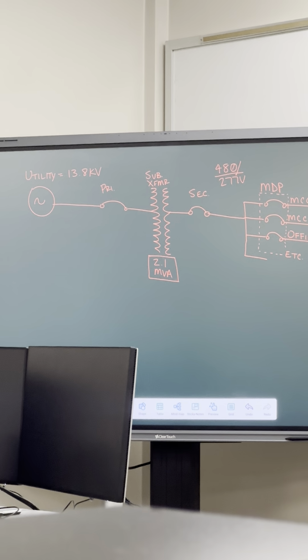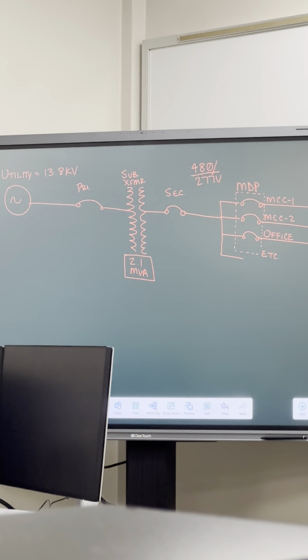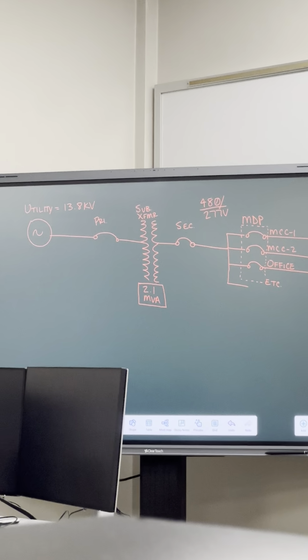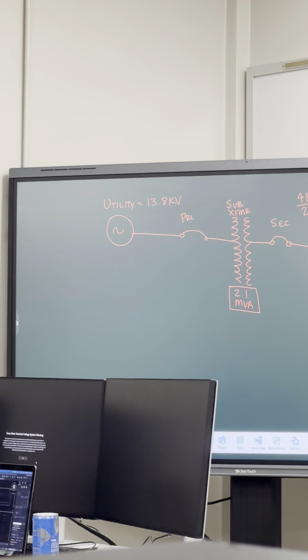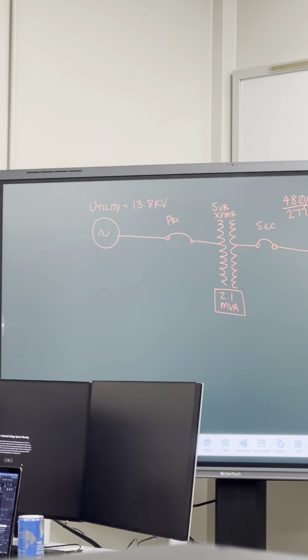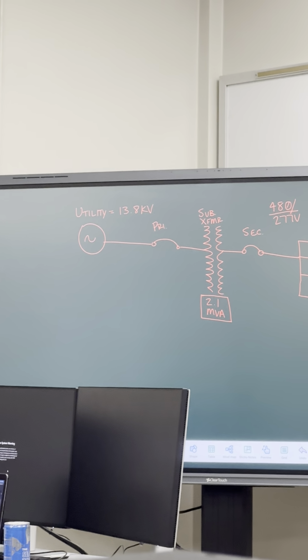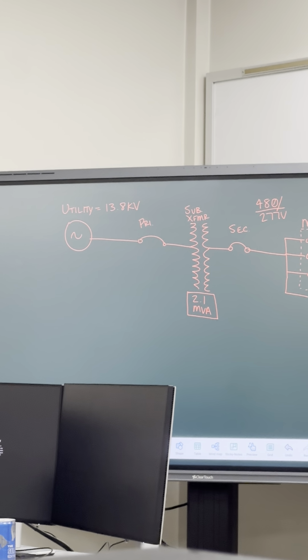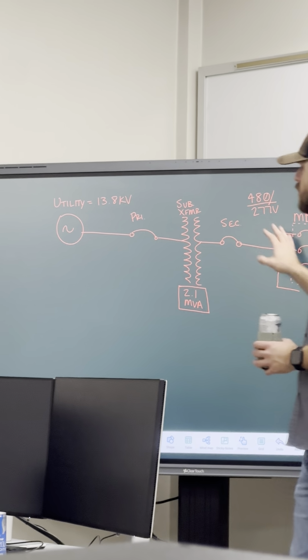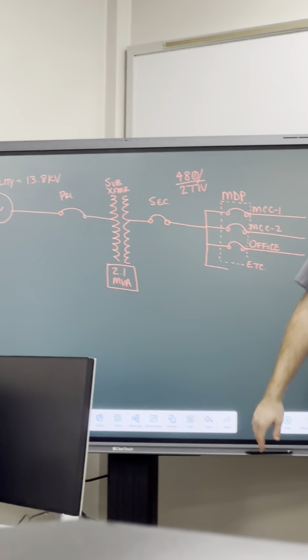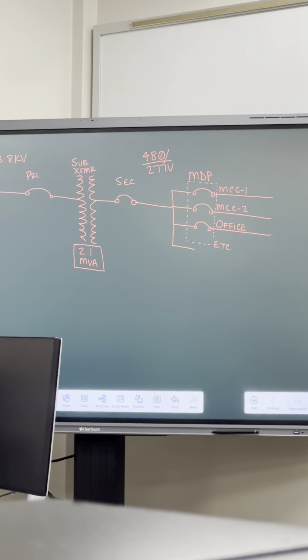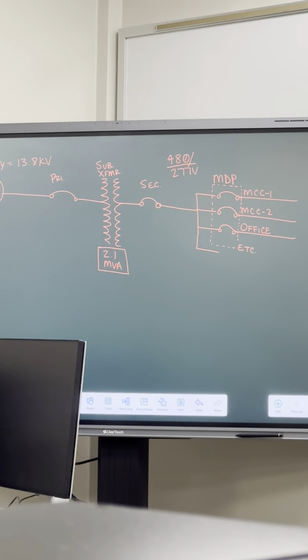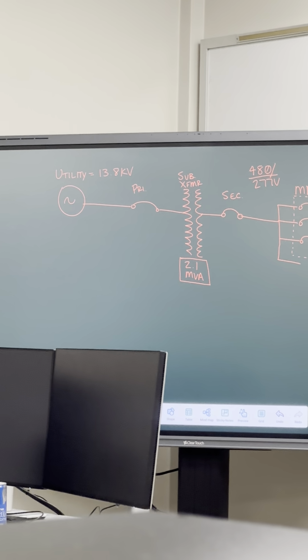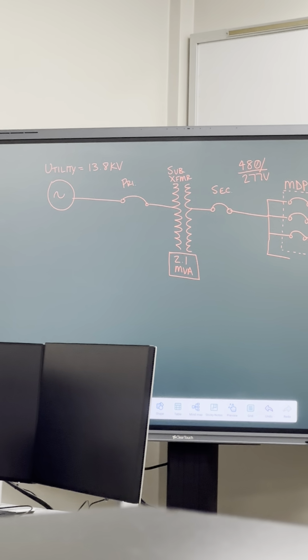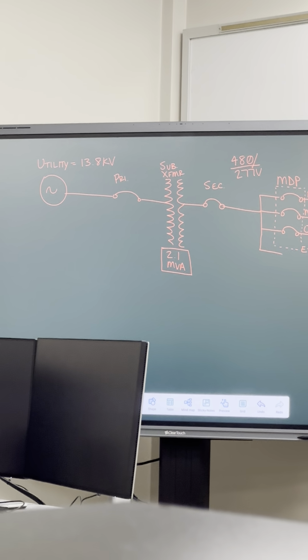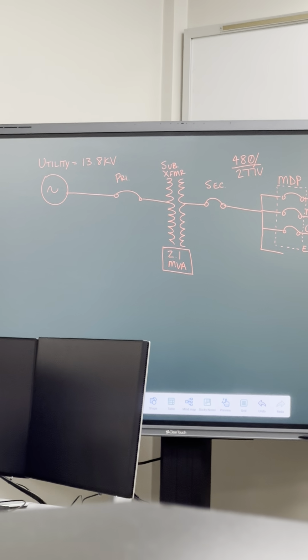So when we look at that option B, 1,000 volts nominal or less, is that applicable to our substation transformer? No, right? Because we have over 1,000 volts on that primary side. Again, that nominal value there, it doesn't care if it's on primary or secondary, it's talking about both, because you can have step up and step down transformers. So it doesn't care what side it's on. So that option B that we used last week for our office feeder, or our office transformer, is not applicable to us. So we need to kind of look at our other options.